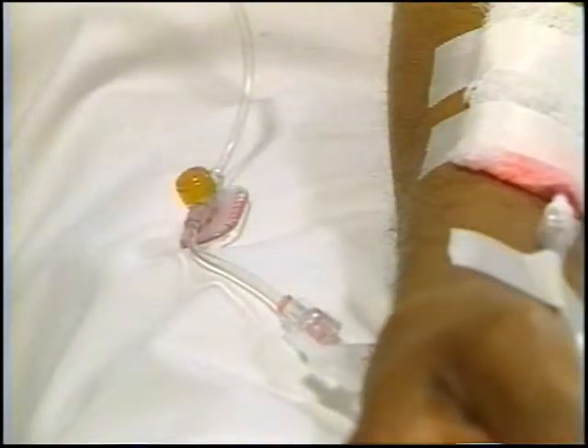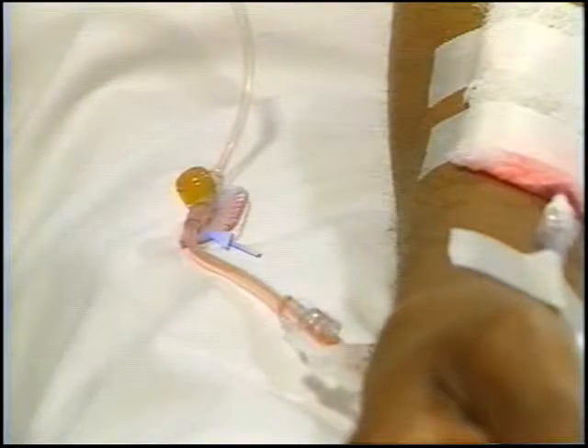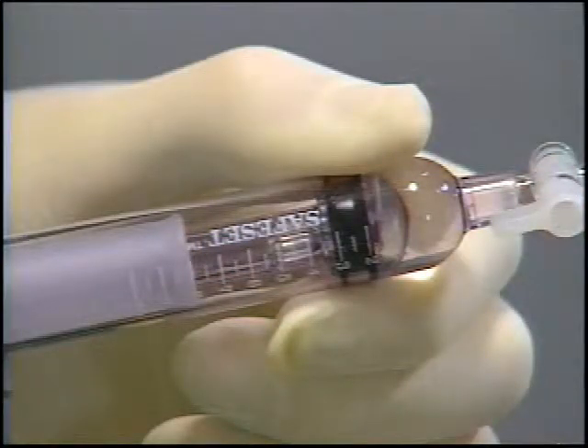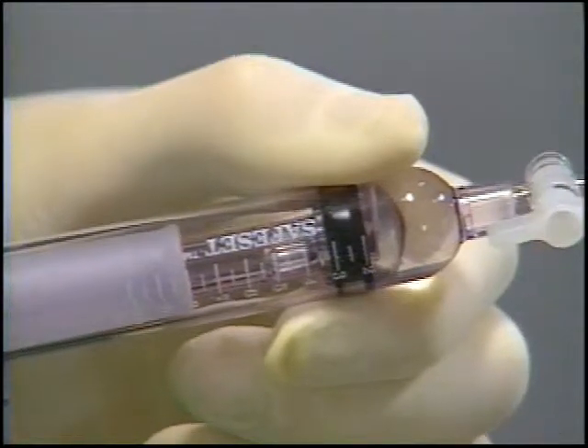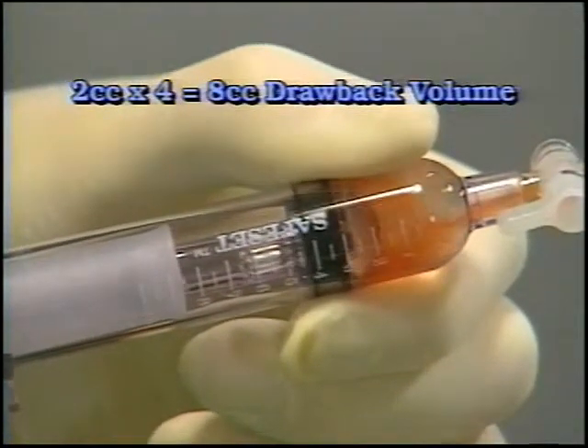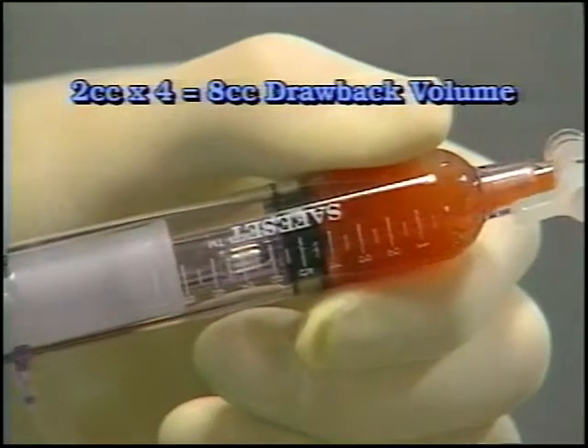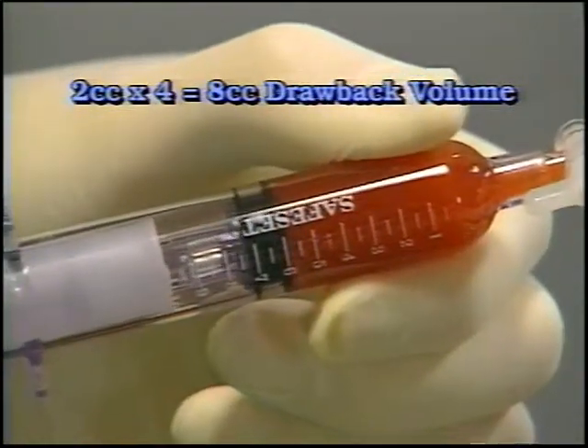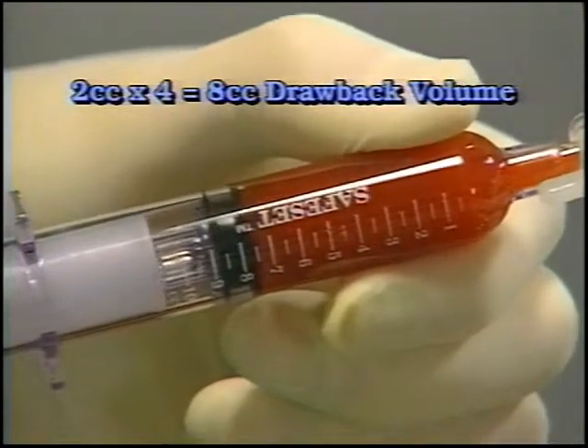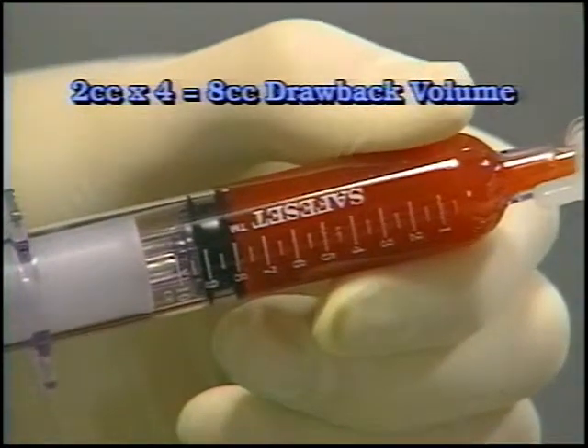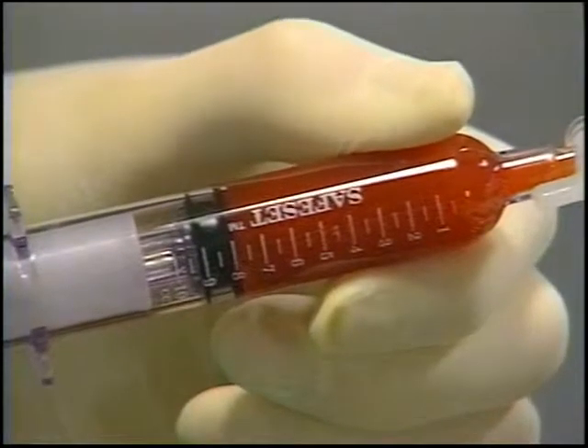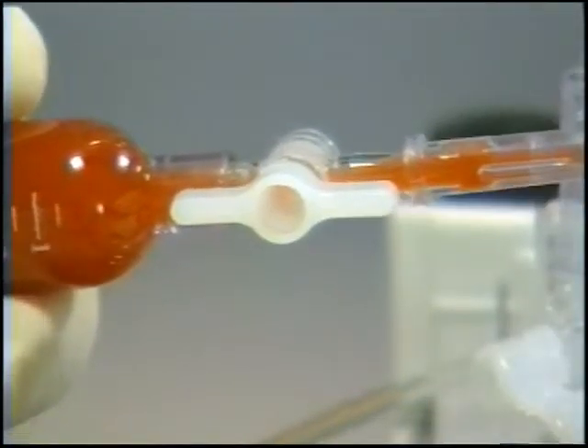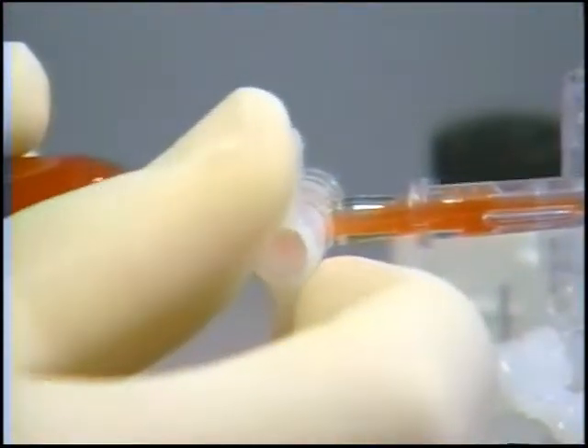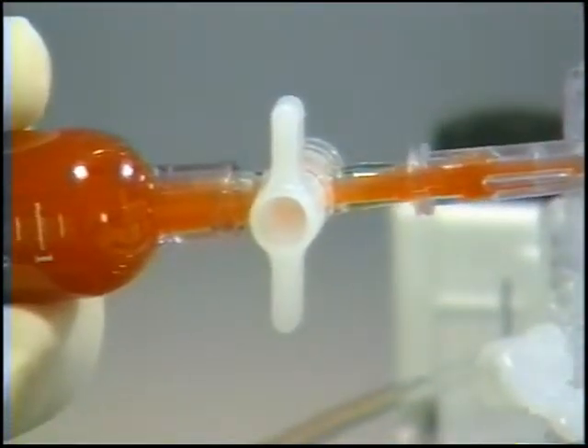To determine the appropriate volume for aspiration, note when the blood reaches the port from which you will draw your clean sample. Then note the volume in the reservoir and multiply the reservoir volume times 4. If the volume is between marks, round up, multiply by 4, and continue to fill until that volume is contained in the reservoir. Once an appropriate volume of blood has been aspirated, turn off the one-way stopcock at the tip of the reservoir. This will ensure that you draw a clean sample from the patient and not from the reservoir.